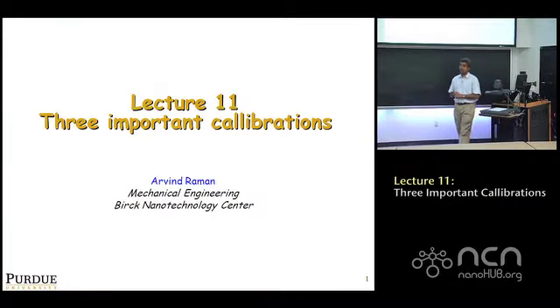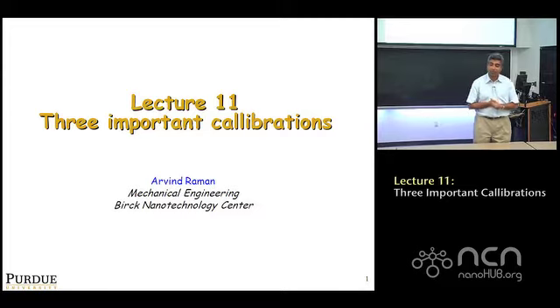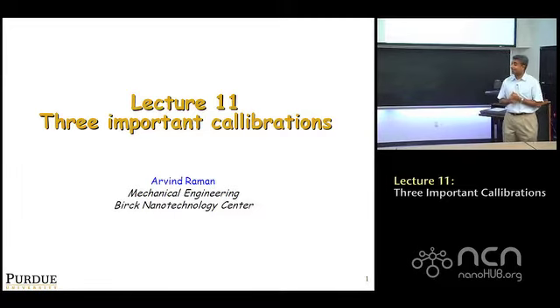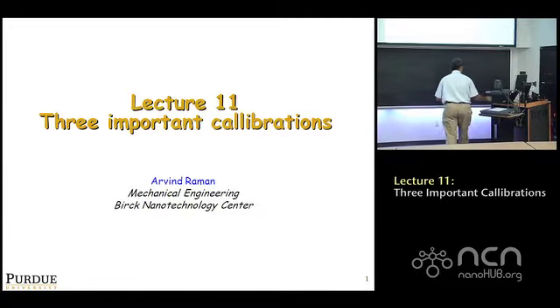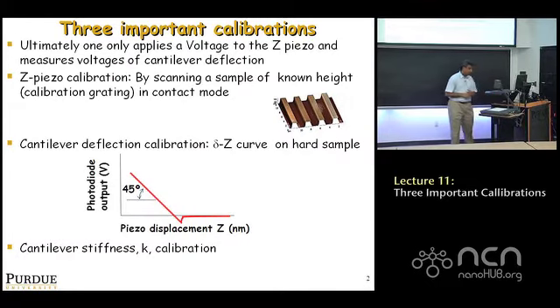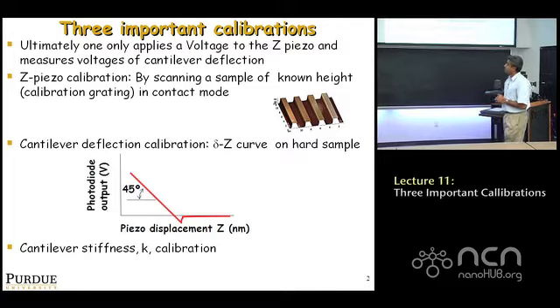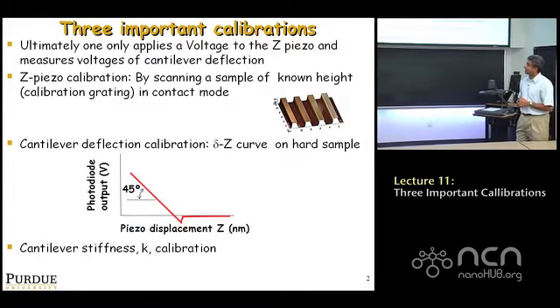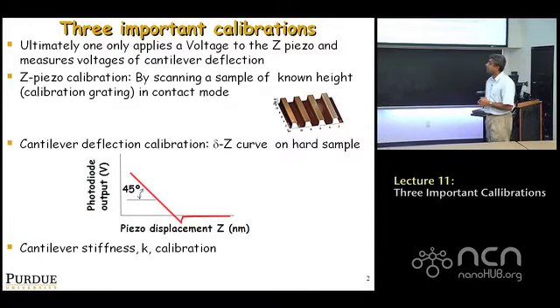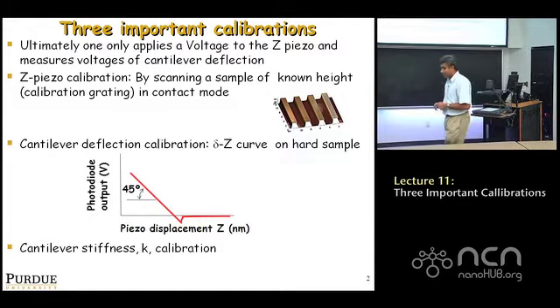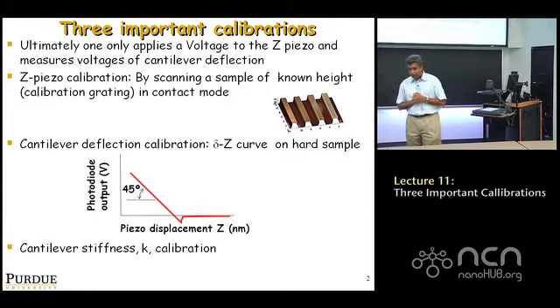Okay, so now we're going to talk today about three important calibrations that most of you need to know while making any AFM measurement. And the three calibrations are the following. The first is what's called the Z-piezo calibration. The second is the cantilever deflection calibration. And the third is the cantilever stiffness calibration.